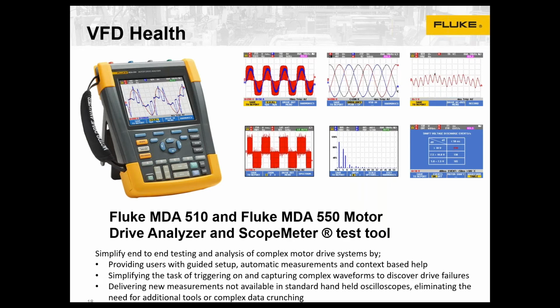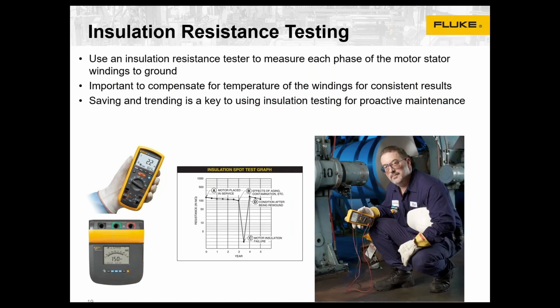So when a user picks a particular measurement, the tool will show you how to connect it up, where to connect the probes. It'll automatically set itself up to make the right measurements. And then you have the ability, if you want, to save those measurements in a report. This can be very useful for baselining new equipment, or looking to see what good looks like, and then if you have an issue, or on a proactive basis, comparing today's measurements with what good looks like to identify potential failures. Again, lowering costs, minimizing that downtime.